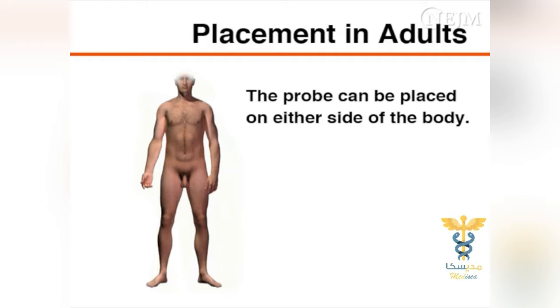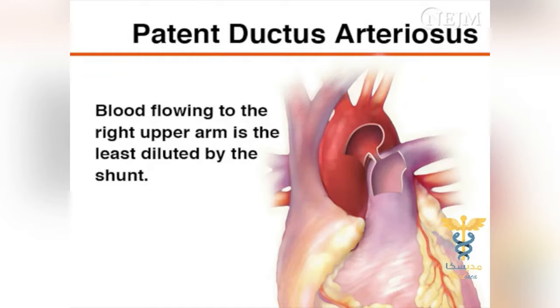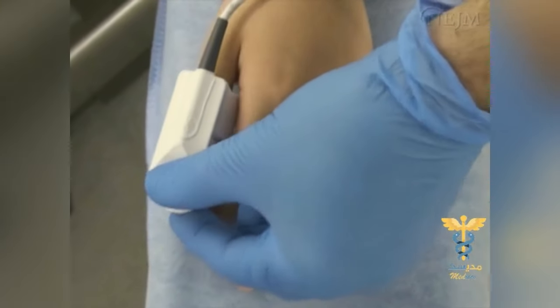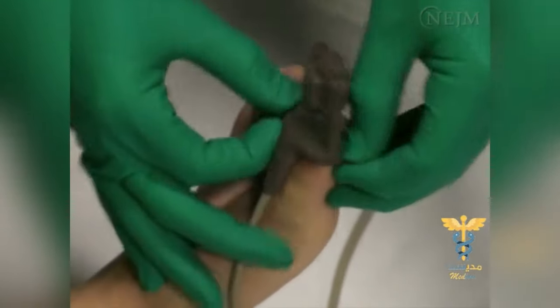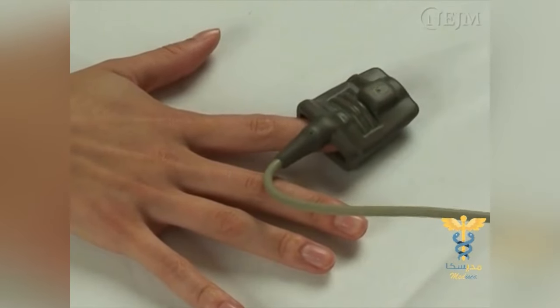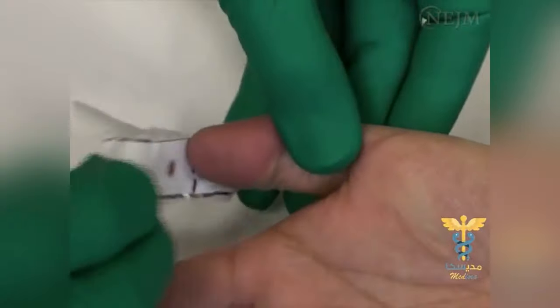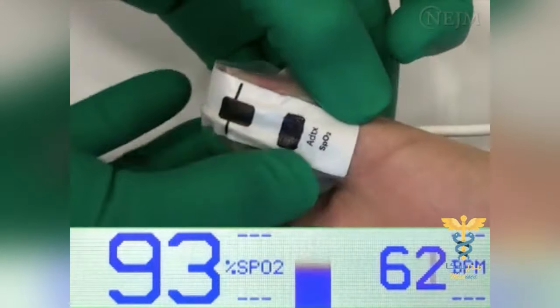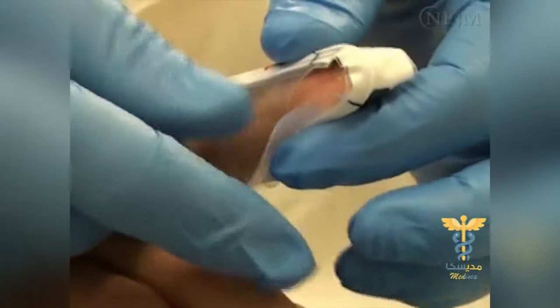In adults, the probe can be placed on either side of the body. In newborns, however, placement on the right upper arm is preferable because of the possibility of a patent ductus arteriosus. Blood flowing to the right upper arm is the least diluted by the shunt and is therefore the most oxygenated. It is important to choose a probe that is the right size for the patient. If the probe is not the right size, the light-emitting diodes may not line up correctly with the photodetector and will provide inaccurate data. Venous pulsations may occur if a probe is too small or is placed too tightly on the finger, resulting in a falsely low pulse oximeter reading. Pulse oximeter probes with adhesive sensors may minimize motion and may yield more accurate results than non-adhesive sensors.